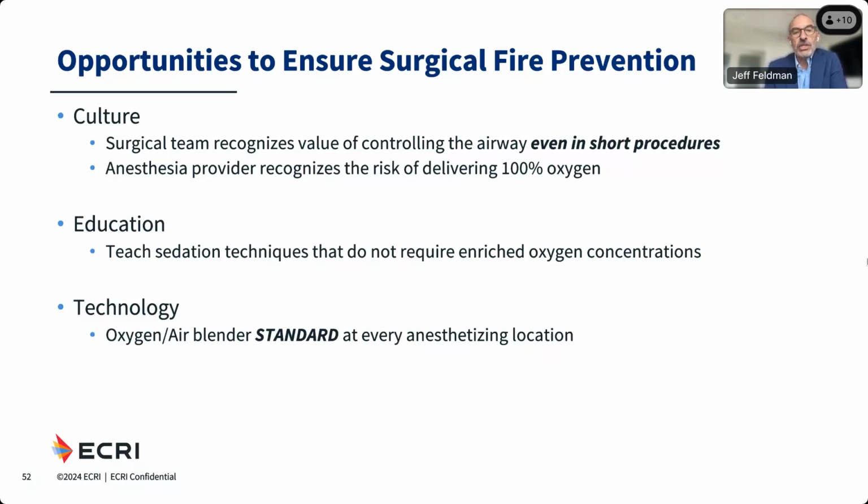Educationally, there is opportunity to teach sedation techniques that can be quite safe, but do not require providing enriched oxygen concentrations. And from a technology perspective, oxygen air blender technology that allows you to lower the oxygen concentration that's delivered is well established and exists. It's an old technology. It is not currently standardized in every anesthetizing location, and having that available would facilitate safer practices.